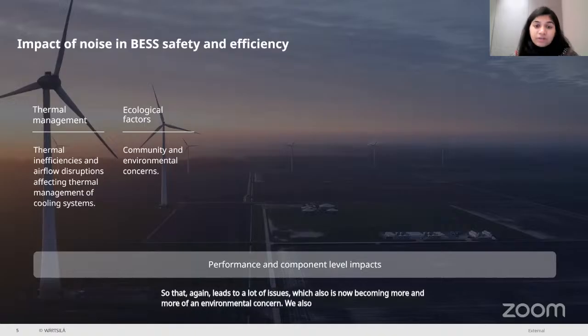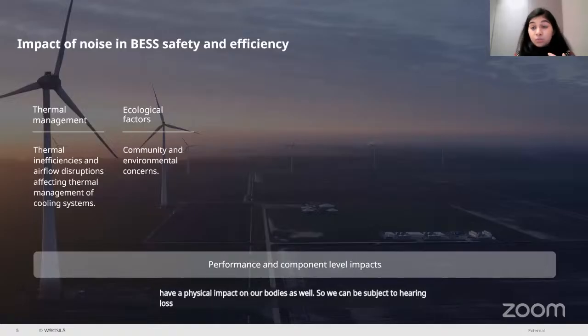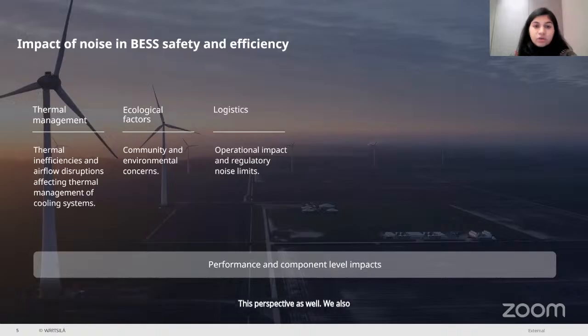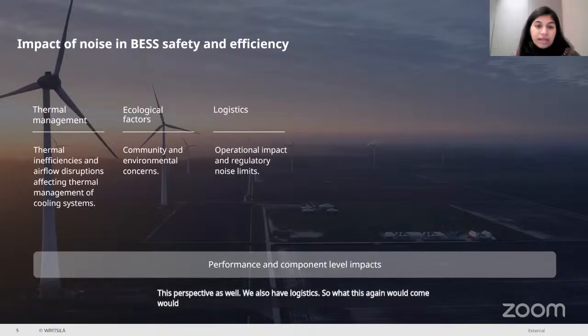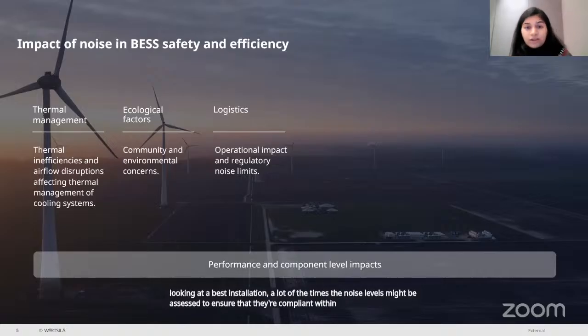We also have community level impact, because high levels of noise can lead to potential conflicts, and not just from an annoyance point of view but also from a health point of view, because it can lead to a reduced quality of life. Over time, noise does have a physical impact on our bodies. We can be subject to hearing loss, psychological issues and even cardiovascular issues over time. So it becomes absolutely important that we address noise from this perspective as well. We also have logistics, which essentially means site selection and planning. When we're looking at a BESS installation, a lot of the time the noise levels must be assessed to ensure they're compliant with the local regulations and the limits present in those regions, so that we can minimize the disturbances to nearby communities.